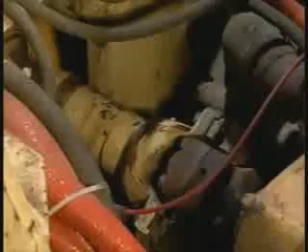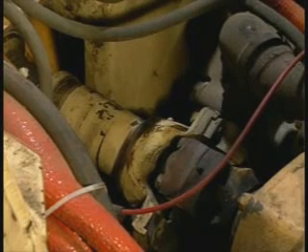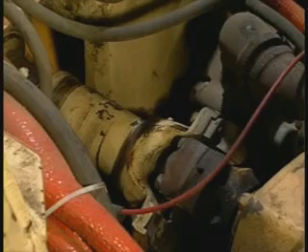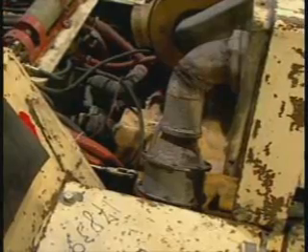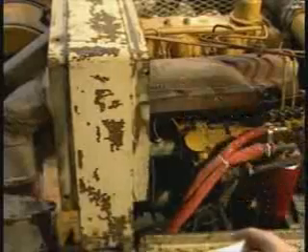Adequate guarding is required to protect fuel, hydraulic, and electric lines when such lines pass near rotating parts, such as belts. Another rotating part is the drive shaft. Should shaft failure occur, fuel lines, hydraulic lines, and electrical wiring could be damaged. Therefore, additional guarding is needed. The regulation is meant to prevent the spray from ruptured hydraulic and lubricating oil lines from being ignited by contact with engine exhaust system component surfaces, such as the exhaust manifold and the exhaust pipe.